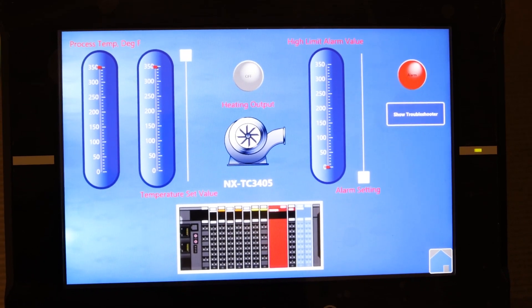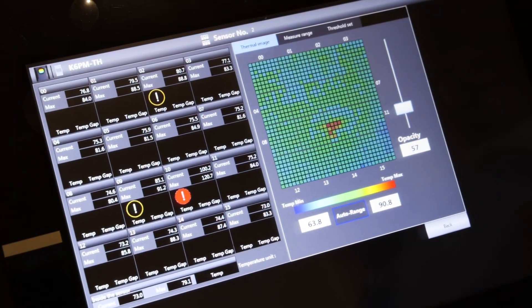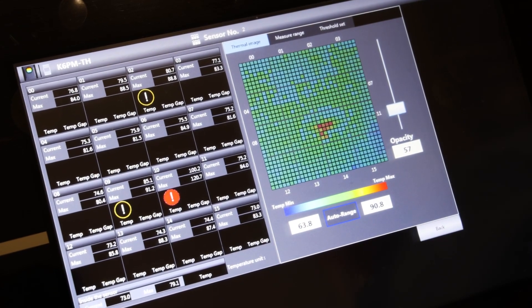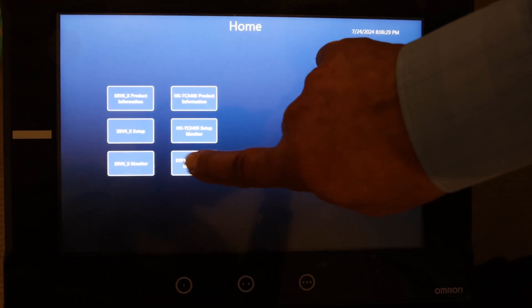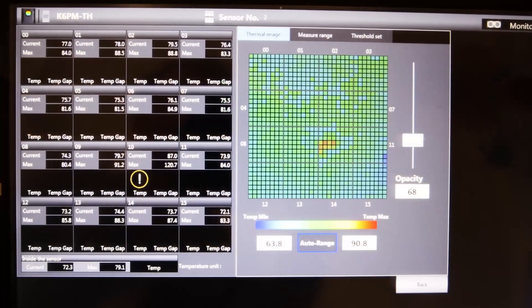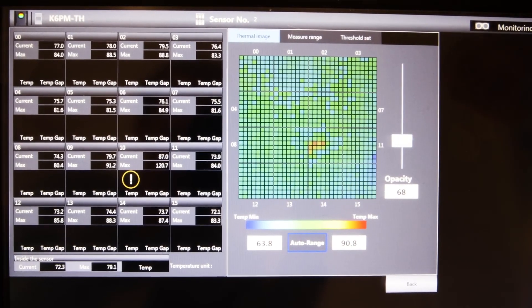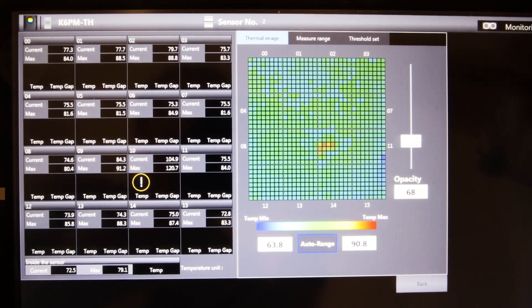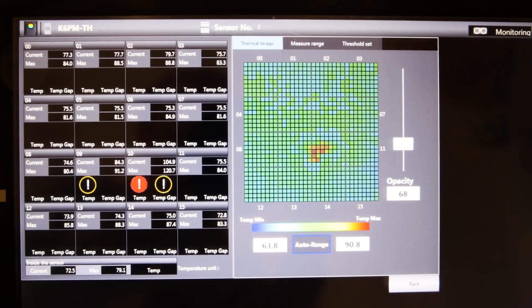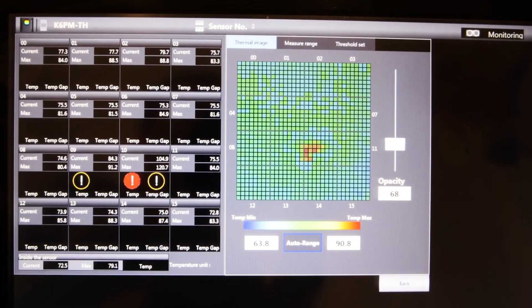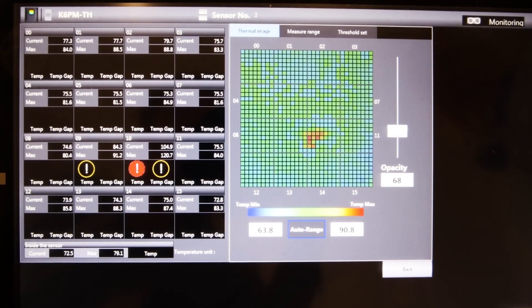To illustrate how it all works, please turn your attention to the heater controls on the NA screen. We can set the heater temp using the slider control. This will cause a rapid temperature rise in camera two's field of view. We can see the heater temperature rising. Now, select the K6PM-TH thermal monitoring button and go to the camera two image. We will begin to see a color contrast change in Region 10 and very quickly see a yellow warning, then red alarm indicator as the temperature rises, illustrating the predictive arrival time function. You can see the red indicator and temperature in that region on the controller.